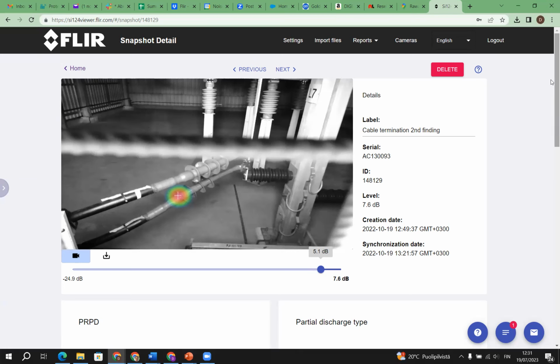They say that they clean and check everything, so how can I say my camera is proving them wrong? But then another person from the customer said, hey, we clean it, but we didn't clean the whole substation because, as you know, shutting down a substation for a couple of days is very expensive, extremely expensive. So they started cleaning, and at some point they said we need to restart it because we're losing a lot of money. So they restarted it and didn't clean this area by the windows, so the camera was totally right.